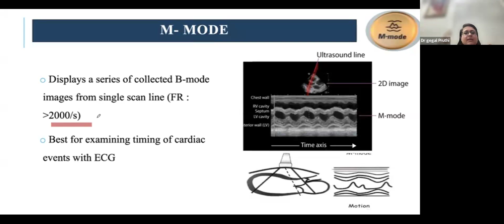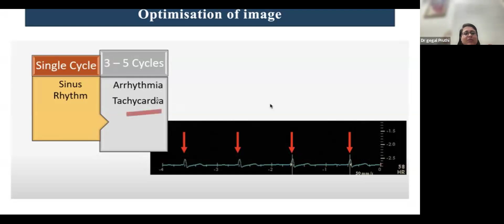Coming to image optimization, first you should know how many cycles you should take. If there is no arrhythmia or tachycardia, if it is in sinus rhythm, a single beat acquisition is enough. Otherwise, for arrhythmias or tachycardia, at least 3 to 5 beats should be acquired. For optimization of the image, you should know about focus, sector size, Doppler optimization, depth, zoom, gain, time gain compensation, and lateral gain compensation, which we'll see one by one.